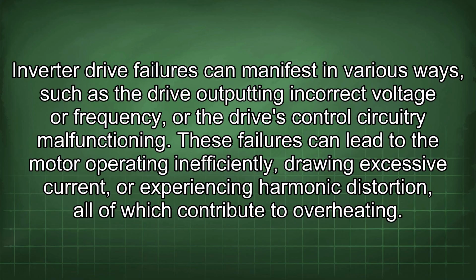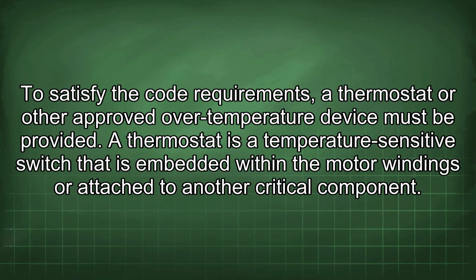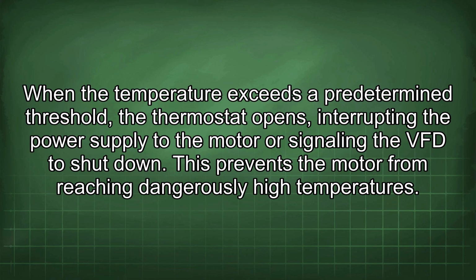These failures can lead to the motor operating inefficiently, drawing excessive current, or experiencing harmonic distortion, all of which contribute to overheating. To satisfy the code requirements, a thermostat or other approved over-temperature device must be provided. A thermostat is a temperature-sensitive switch that is embedded within the motor windings or attached to another critical component. When the temperature exceeds a predetermined threshold, the thermostat opens, interrupting the power supply to the motor or signaling the VFD to shut down. This prevents the motor from reaching dangerously high temperatures.